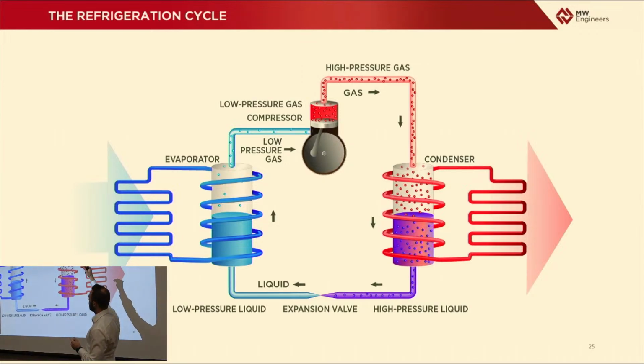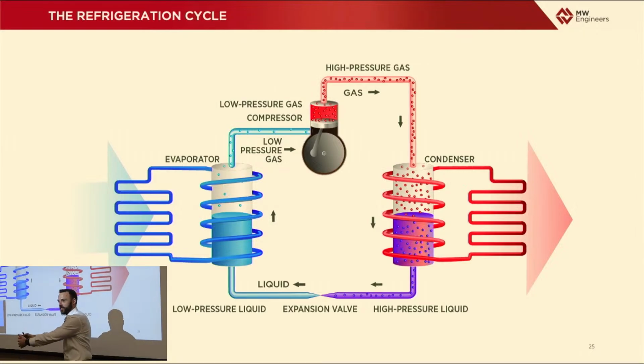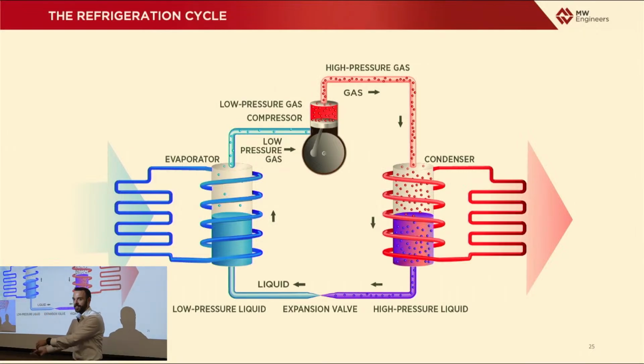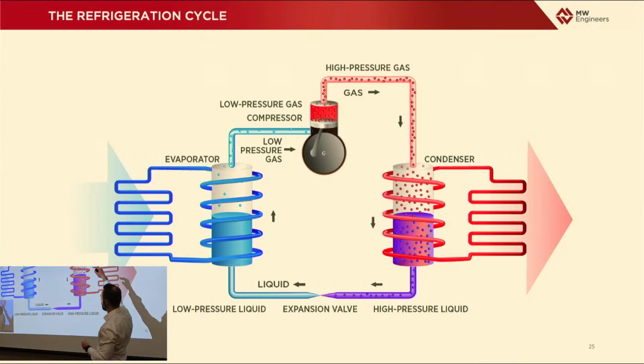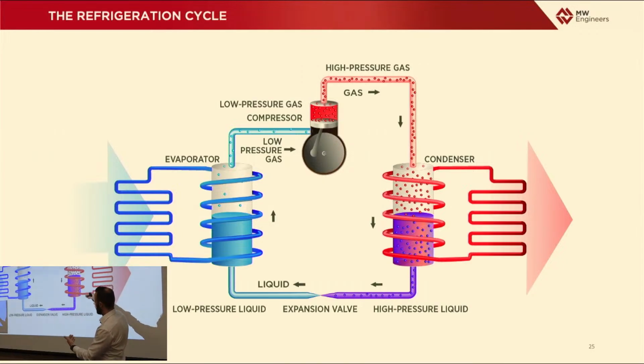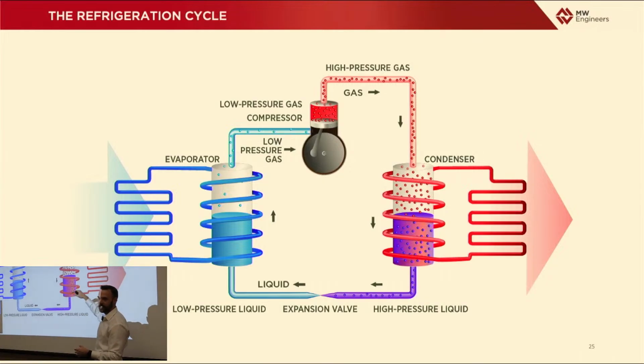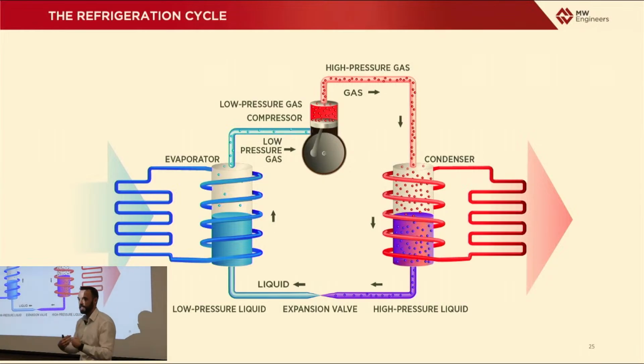The high pressure, high temperature gas now goes to the condenser. The condenser would be on the outside of your refrigerator, or if you have air conditioning at your house, it's what everybody thinks is the air conditioner outside—that's really a condenser. So this gas goes to the condenser, and through the condenser, the high pressure, high temperature gas condenses into a high pressure liquid. So we've changed phases, and through that phase change, we've released or removed energy from this refrigerant.